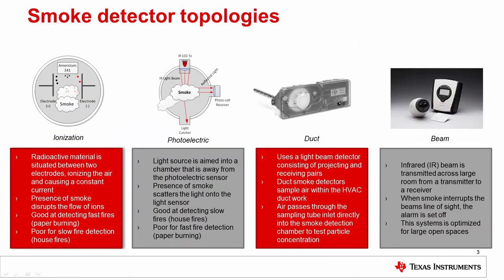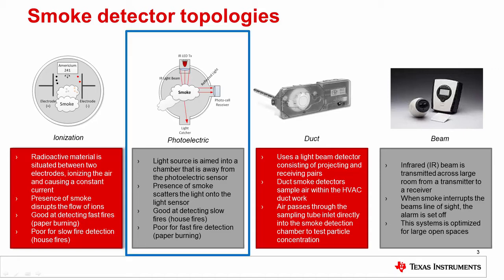There are different types of smoke detectors, each of which has its own benefits and shortcomings. By far the most popular types on the market today are ionization detectors and photoelectric detectors. There are also combo detectors available which contain both sensors in a single unit. Duct and beam detectors are designed for specific applications, but at their heart they use a specialized form of a photoelectric sensor to detect smoke. Because ionization sensors are facing ever-increasing environmental regulation, the remainder of this presentation will be focused on the photoelectric detector.